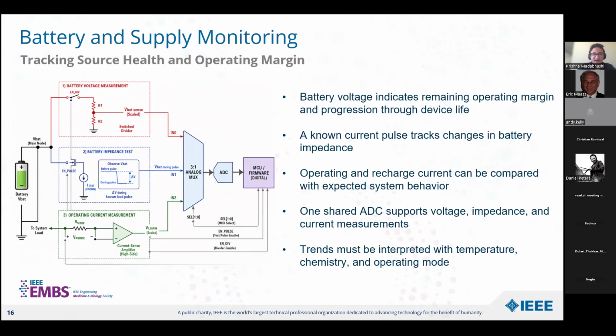That voltage will provide information about the available operating margin, but voltage alone will not show how well the battery can support any loads we might have. Further, the system can apply a known current load and measure the voltage change, and the ratio should give us the battery impedance. As the impedance increases, the battery may produce more voltage droop during high current activities, even while its resting voltage still appears acceptable.